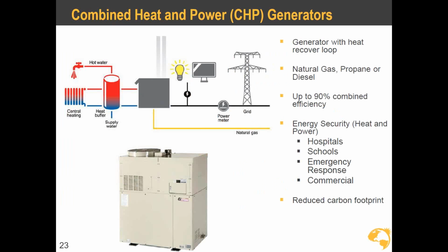Combined heat and power generators - what is a CHP generator? It's a traditional generator, an internal combustion engine, except it has a heat recovery loop on the engine casing and exhaust jacket. When there's a heat demand in the building, whether residential or commercial, this generator turns on, it produces electricity, and one of the byproducts of producing that electricity is heat. That heat is then captured to do either space heating or domestic hot water.